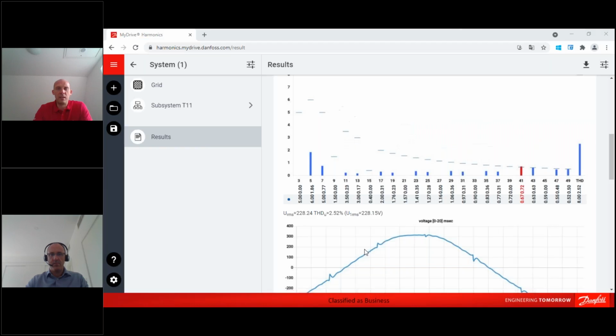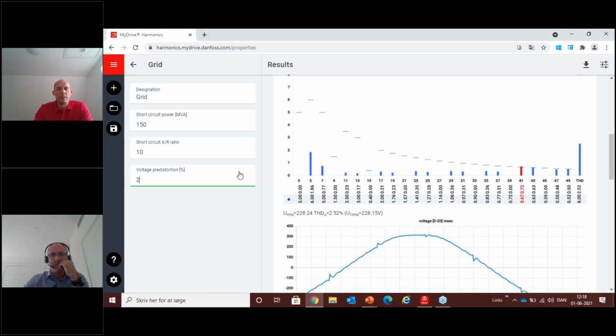And maybe one thing that I didn't mention here in the tool, you can actually go in here and specify a pre-distortion level. So if you say that I probably already have 3% voltage distortion on the supply grid before I start installing anything, then you can put in the value here, and then you can recalculate. It's of course difficult to do exact because you don't know the angle of the different harmonics, you don't know how big the individual harmonics are, but this at least gives you an indication of the total distortion. So I think this is useful, but it's not perfect. So it's something to be aware of.